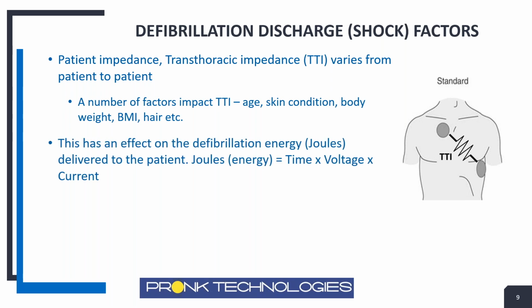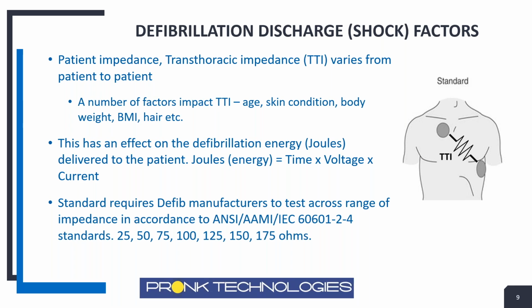And so, of course, you're trying to deliver defibrillation energy in joules, which is a function of time, voltage, and current, to deliver the specified amount of energy to that patient to hopefully recover that patient with the least amount of energy. There is a standard that the defibrillator manufacturers are required to follow to make sure that the defibrillator can work properly within its specifications across this wide range of patients. And there's an AAMI standard that they're required to meet during the manufacturing process. If you or your organization does actual repairs on a defibrillator, where you're actually opening and repairing something, you really want to be following this standard for testing it to make sure it's compliant to the standard.